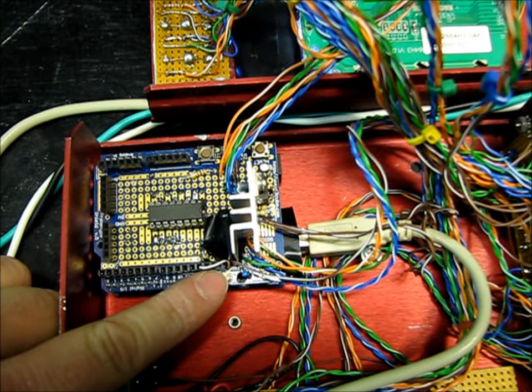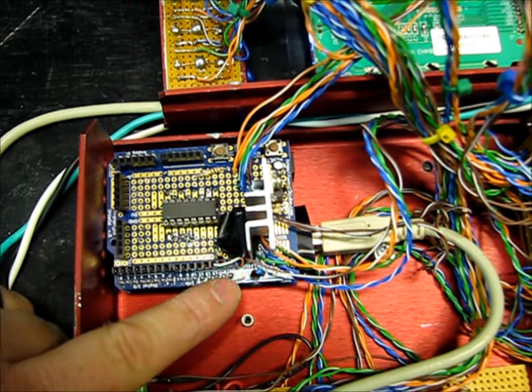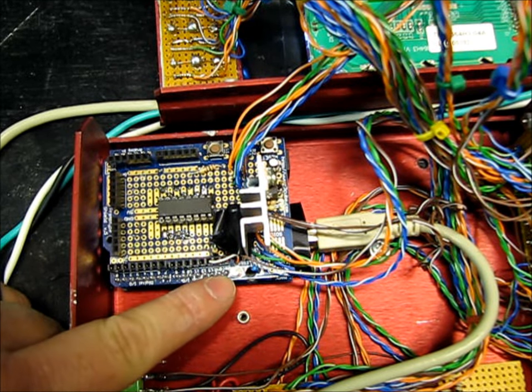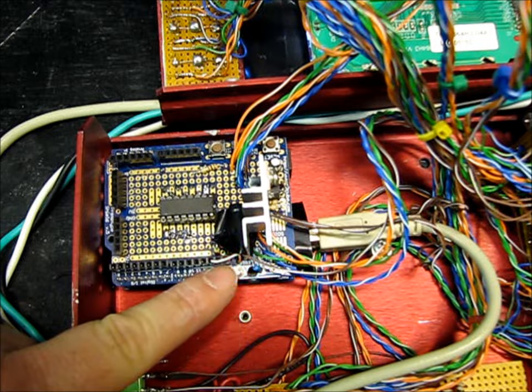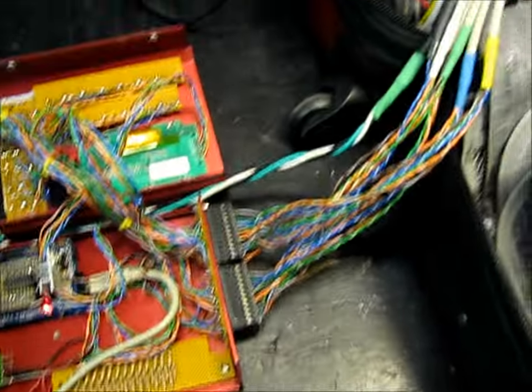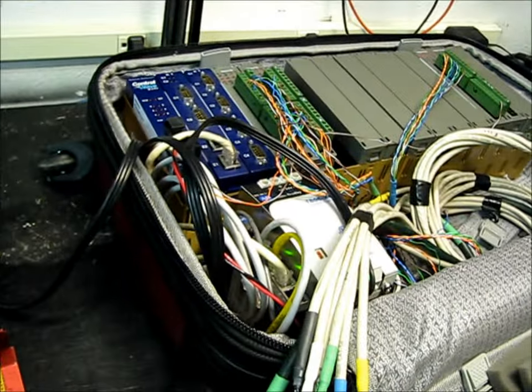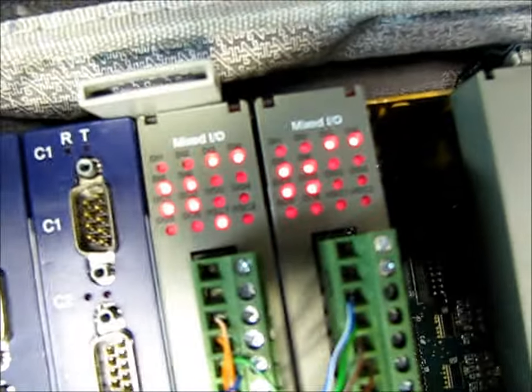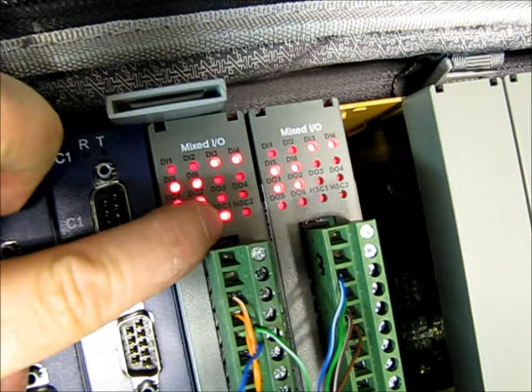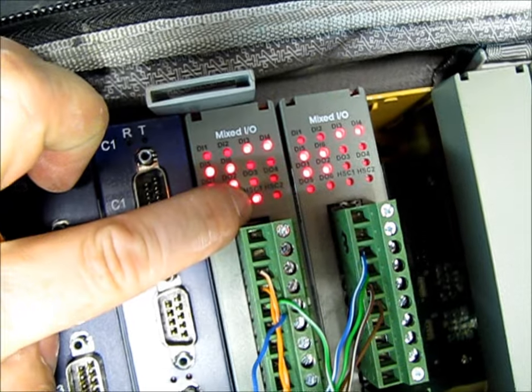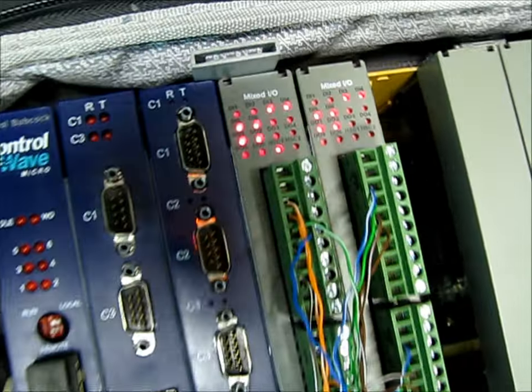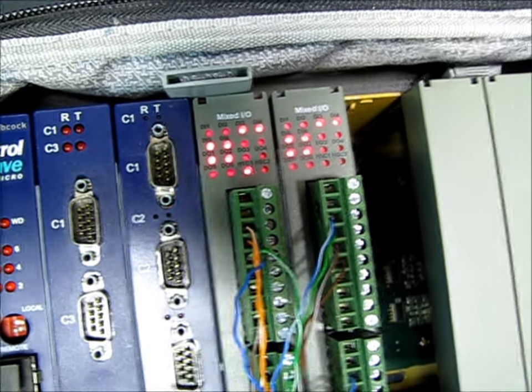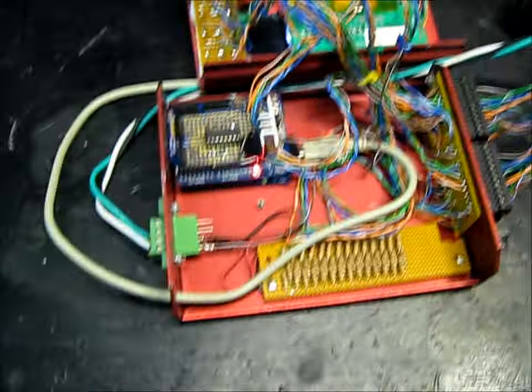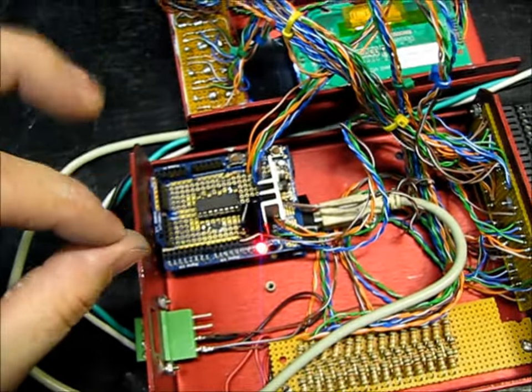This flashing is done on purpose. I have an output here that's flashing at a certain rate, and I'm using that because a lot of times PLCs can have high-speed counters. You can see that this one right here is pulsing with that high-speed counter. High-speed counters are used with flow meters, turbine flow meters, where there's a little turbine that spins and a little magnetic pickup pulses. I built this in because it's another thing I can test.